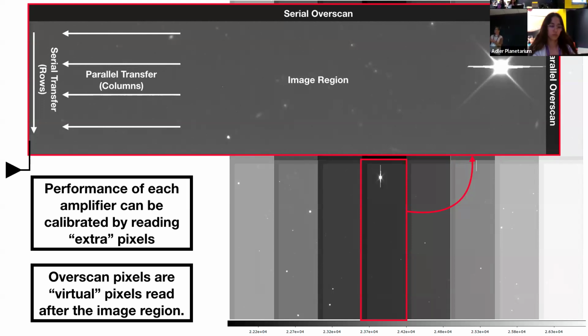So what we generally do, in our bucket brigade, is read a little bit longer than we would need to. So what we actually read is past the end of the CCD. So these are pixels that are not physical. They were never collecting photons. They're just artificially created by shifting the charge, continuing to shift the charge beyond the edge of the actual pixel region. These are called overscans.